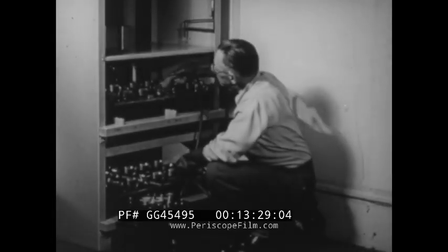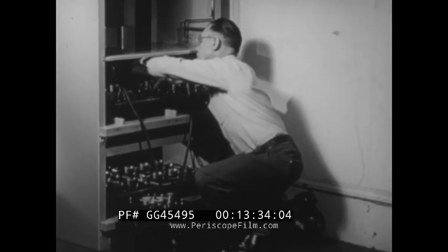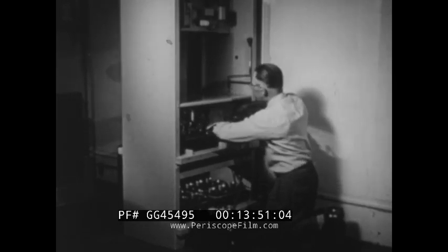In the smaller size battery plants, if the cells will not hold a charge after boost charging, a capacity tester is used in accordance with Bell System Practices. The rated capacity of any cell is related to the size and number of plates. The tester can be set for different battery sizes.